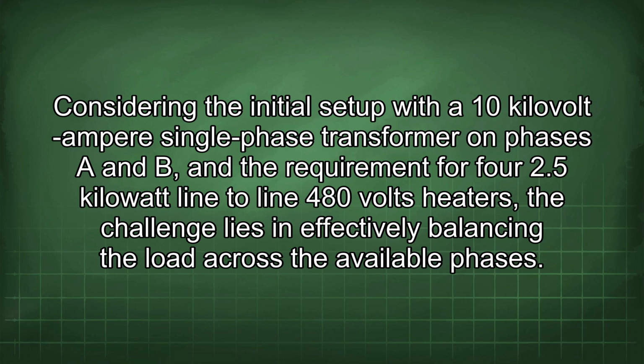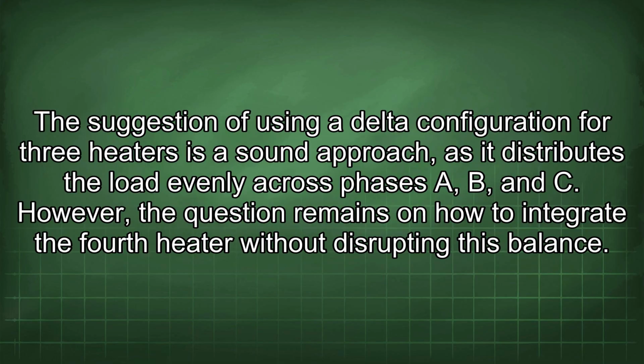Considering the initial setup with a 10 kVA single-phase transformer on phases A and B, and the requirement for 4 2.5 kW line-to-line 480 volts heaters, the challenge lies in effectively balancing the load across the available phases. The suggestion of using a Delta configuration for 3 heaters is a sound approach, as it distributes the load evenly across phases A, B, and C. However, the question remains on how to integrate the 4th heater without disrupting this balance.